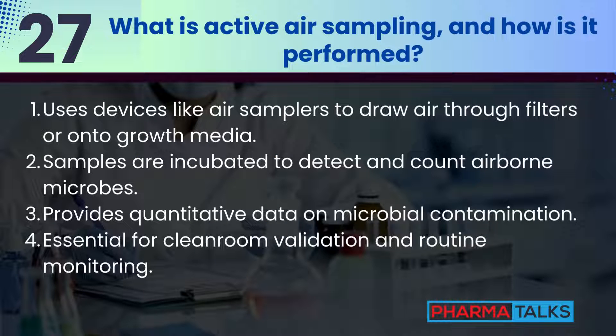What is active air sampling and how is it performed? Active air sampling involves using devices like air samplers to draw air through a filter or onto a growth medium. The samples are incubated to detect and count airborne microbes. This method provides quantitative data on microbial contamination and is crucial for clean room validation and routine monitoring.